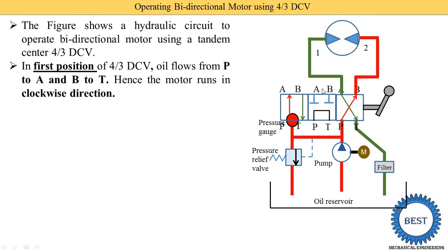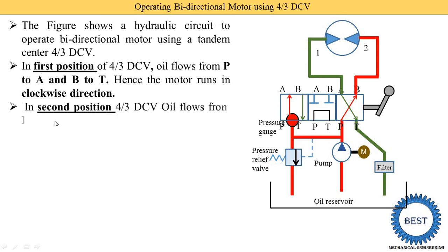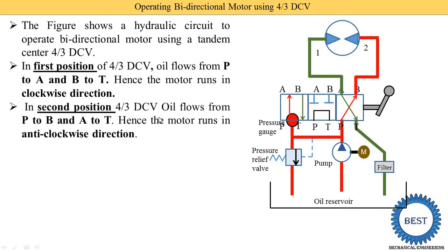Here you see the position of the directional control valve is changed. The directional control valve can be operated by a number of methods — manual, foot valve, solenoid type, or pilot type. Moving the directional control valve to the second position: port P is connected with port B, and port A is connected with port T. In the second position of the 4x3 DCV, oil flows from P to B and A to T, hence the motor runs in the anti-clockwise direction.